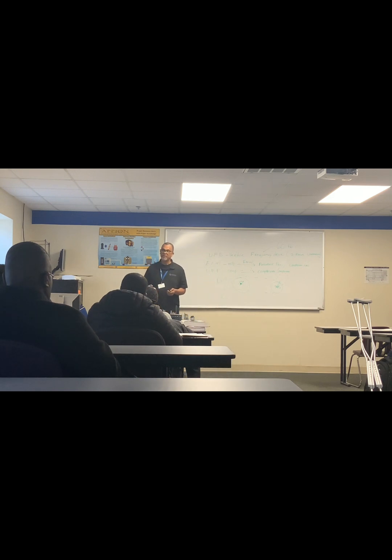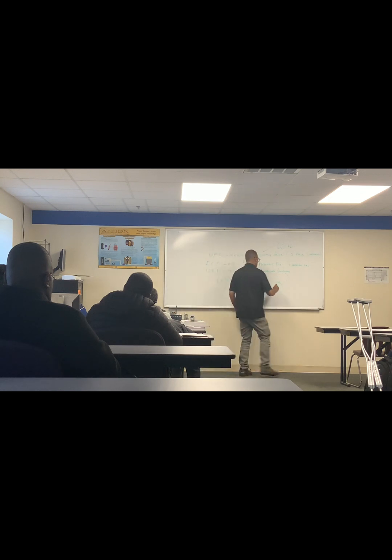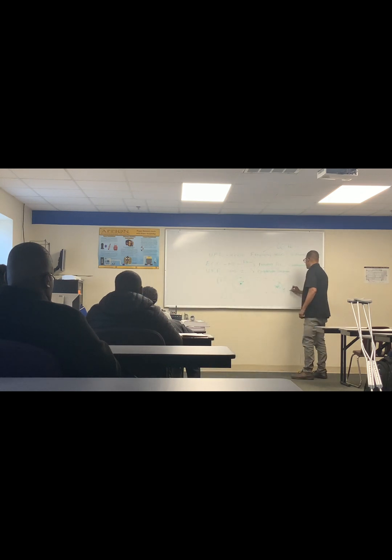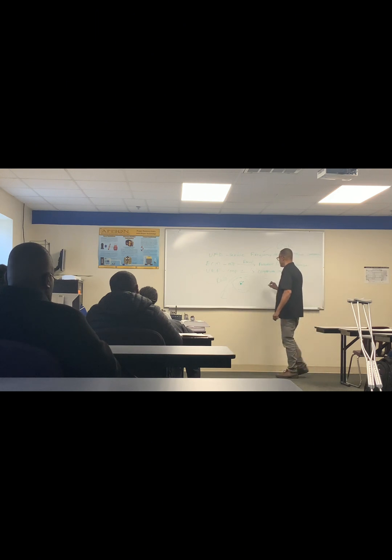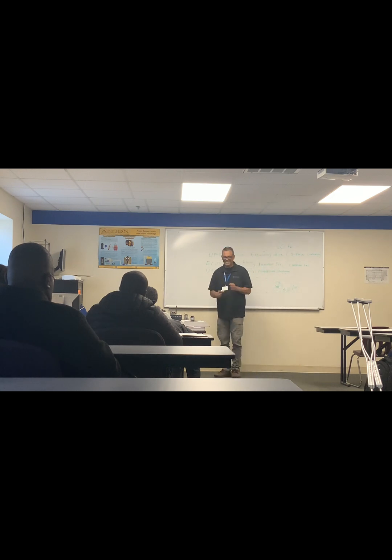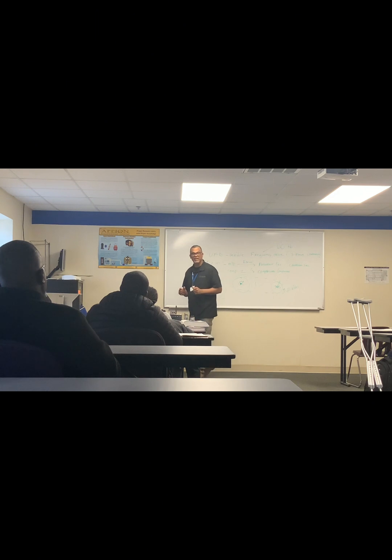So what does 3 to 1 mean? For every 3 rotations of the small pulley, the big one turns 1. So that little motor is going, and the air handler is going whoop, whoop, whoop. It can go faster and faster, but the ratio remains the same. You'll find those in the market and commercial a lot.